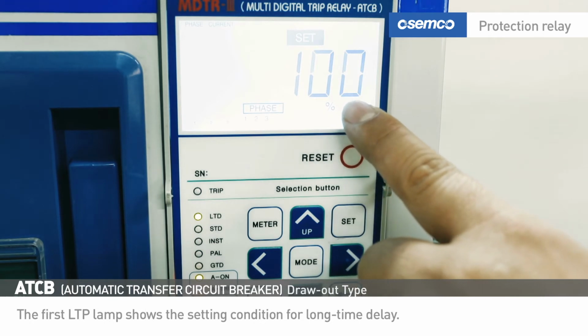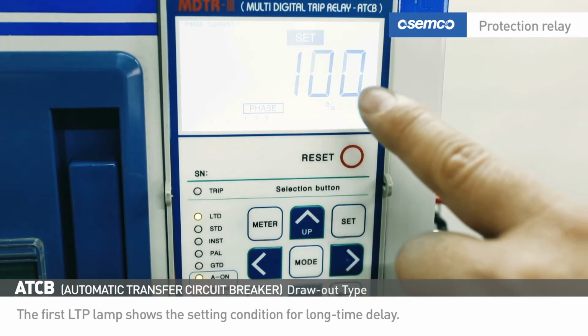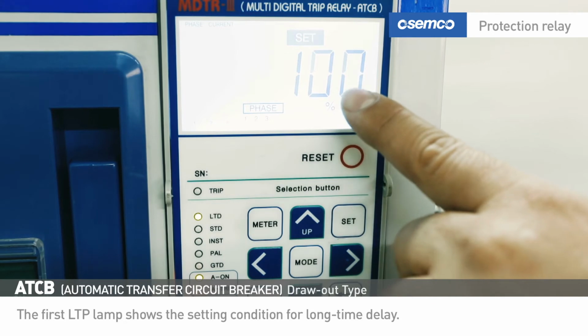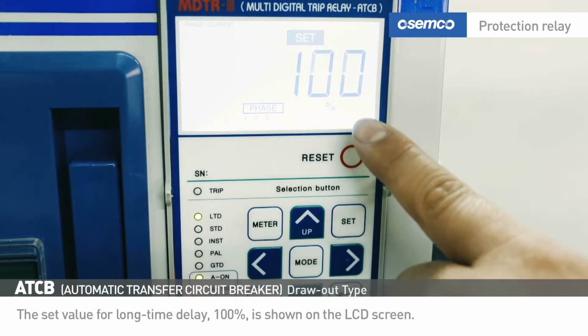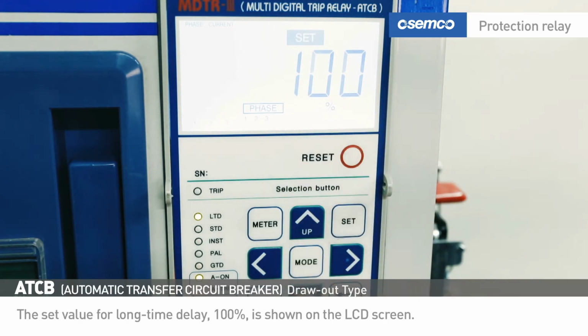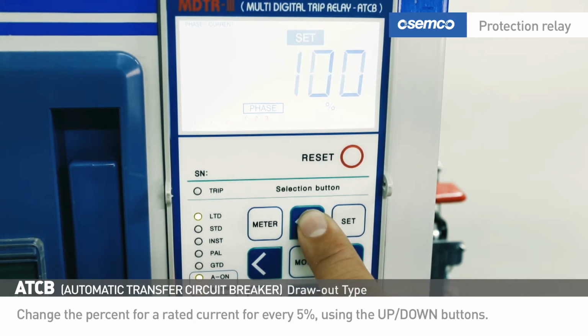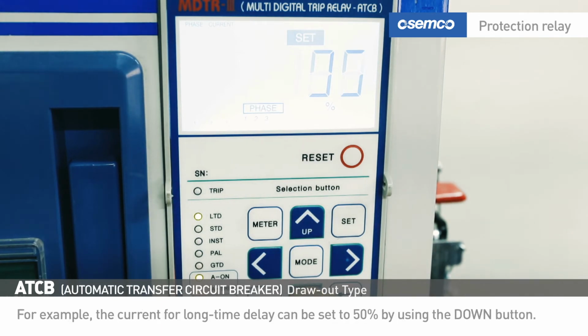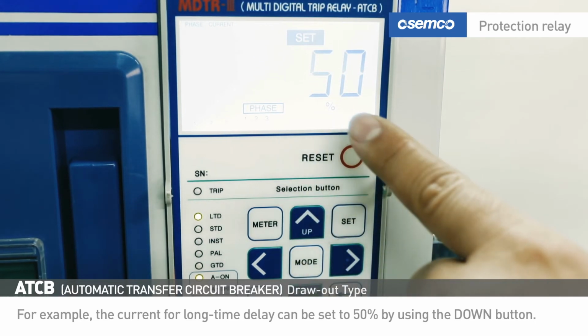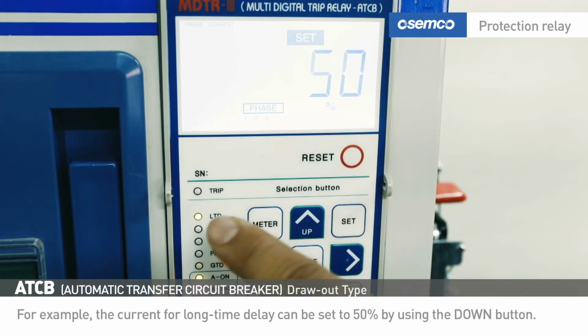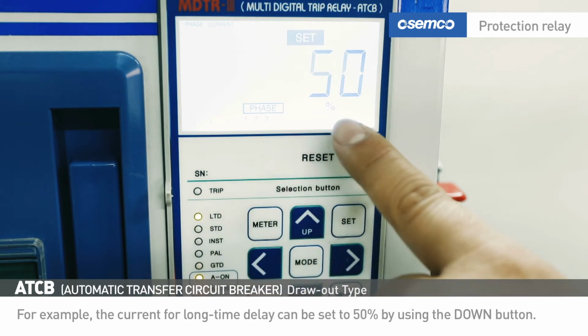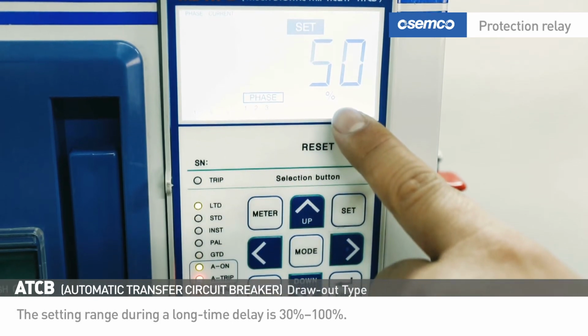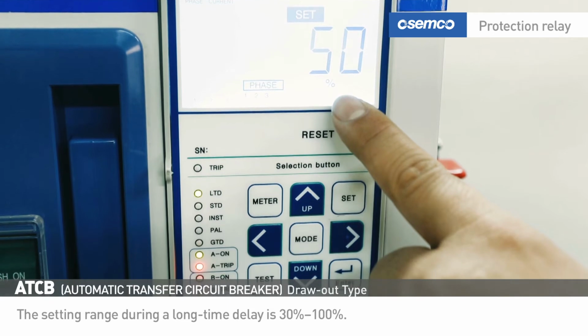The first LTP lamp shows the setting condition for long time delay. The set value for long time delay, 100%, is shown on the LCD screen. Change the percent for a rated current for every 5% using the up-down buttons. For example, the current for long time delay can be set to 50% by using the down button. The setting range during a long time delay is 30% to 100%.